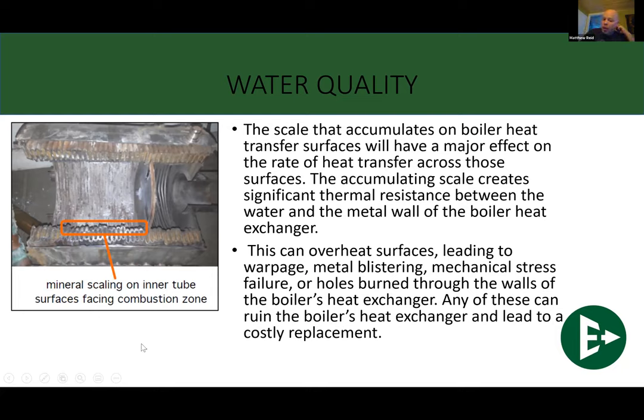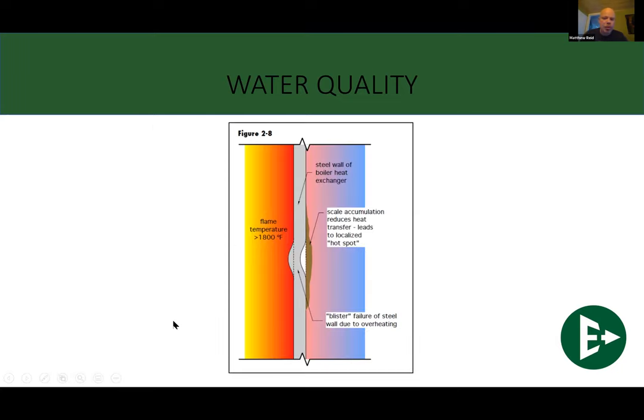Once we start to do that, we start overheating these heat exchangers. Once we do that, we start to really stress them. We will cause blisters on the inside. I'll get to those. And we'll start to talk about the boiler's heat exchanger just completely failing altogether. So we need to make sure we get that taken care of. Here's a picture of what a blister looks like. This is the most common thing that you are actually seeing when you're talking about a cracked heat exchanger.